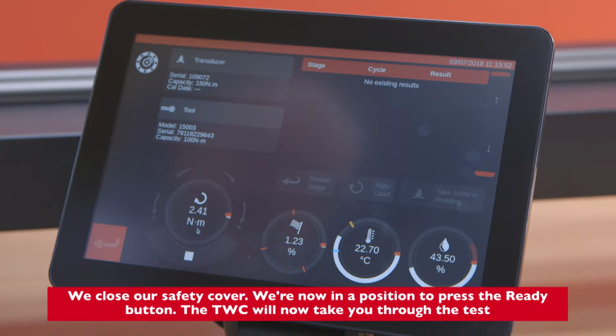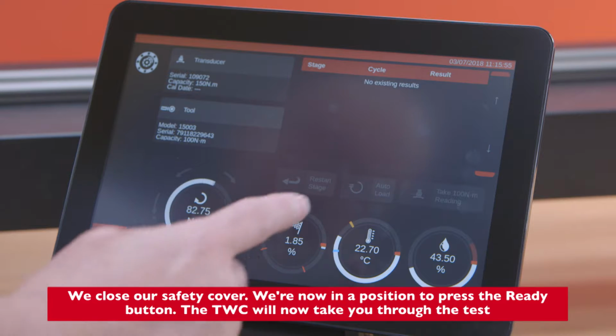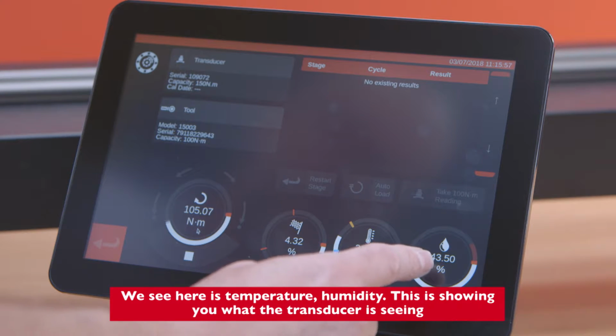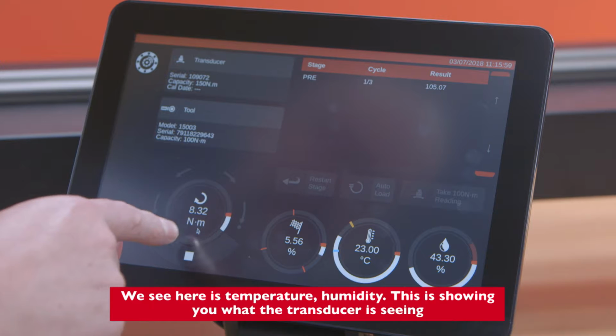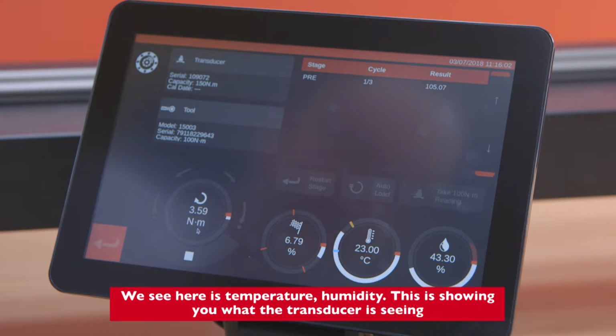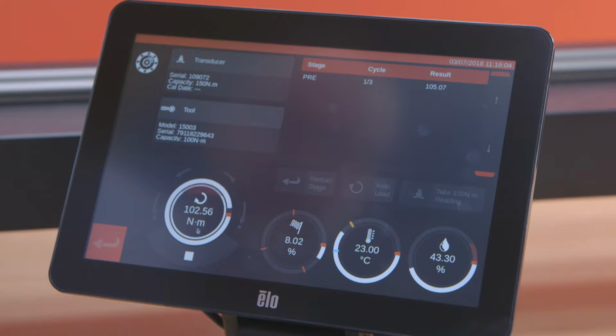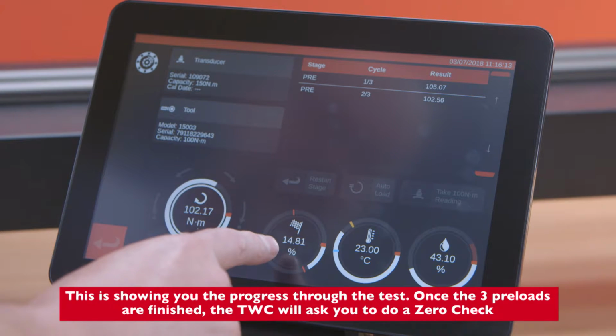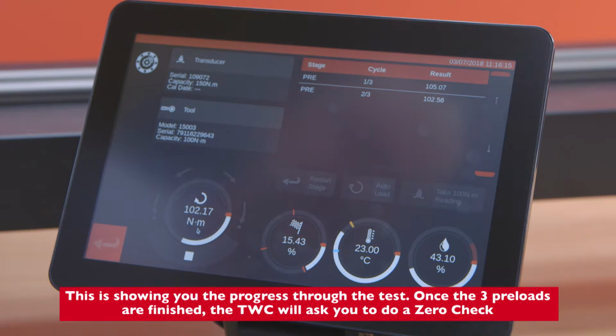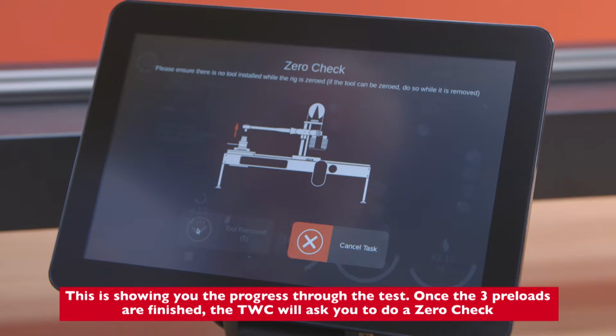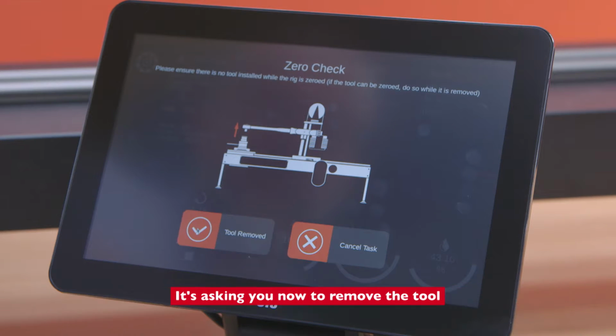The TWC will now take you through the test. We'll see here's temperature, humidity. This is showing you what the transducer is seeing. This is showing you the progress through the test. Once the 3 preloads are finished, TWC will ask you to do a zero check. It's asking you now to remove the tool.